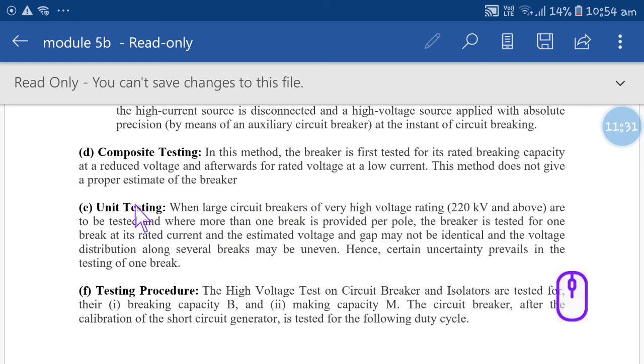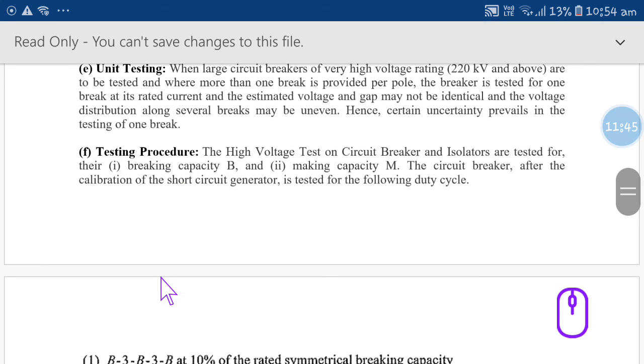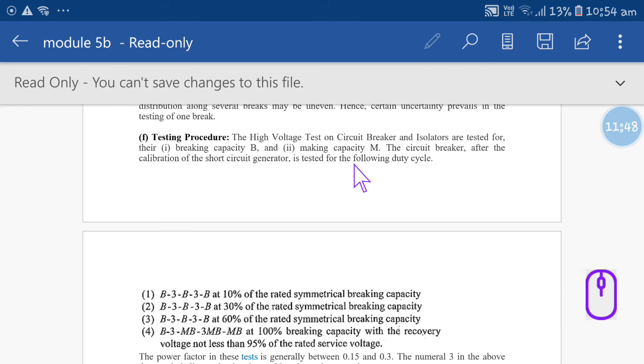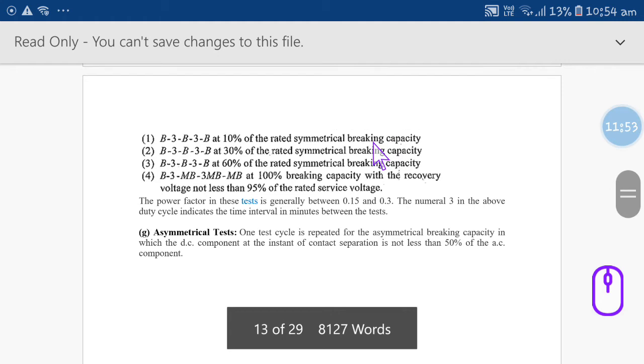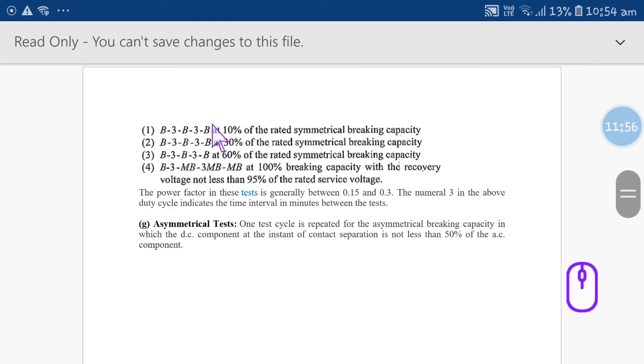Now, what particular break is provided per pole, they are giving, and for more than 220 kilovolt they can also do the test with unit testing. And the testing procedure: if they want to go for high voltage testing on circuit breakers, isolators and all, first they go for breaking capacity, making capacity and all. They can check. See, this list also they have given. B3 and all, this is the rated symmetrical breaking capacity. This is also symmetrical breaking capacity. B3 10%, 30%, 60% rated symmetrical breaking capacity, 100% with recovery.